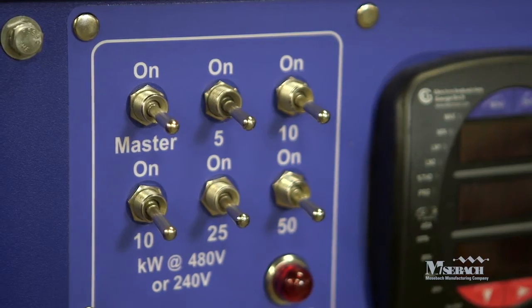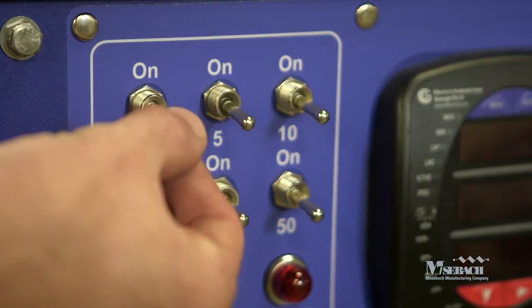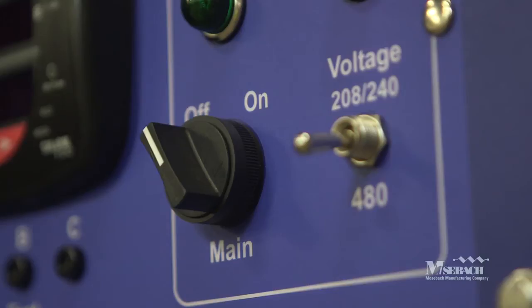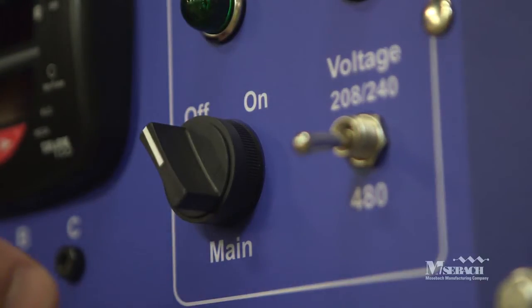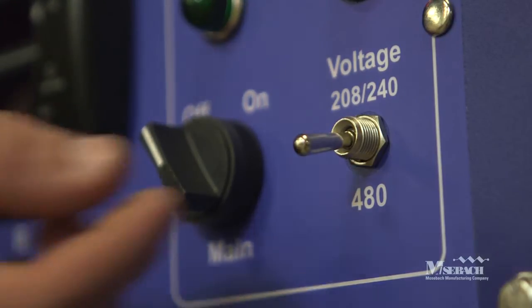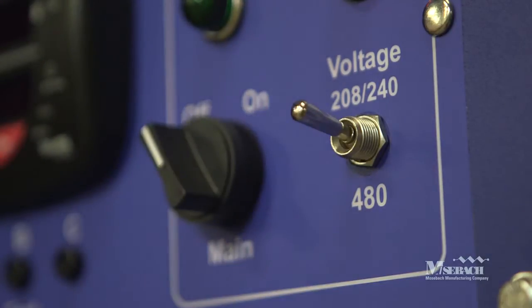Once the load bank is safely positioned, we're ready to begin to set up for a test. First, it's important to set all the switches to the off position. Start with the step switches and put them in the down, off position. Next, verify that the main power switch is in the off position. Finally, it's time to select the voltage. For all 480-volt three-phase testing, make sure the voltage switch is in the down position. For all other testing, including 240-volt and 208-volt three-phase, as well as 240-volt and 120-volt single phase, the voltage selector switch must be placed in the up position.